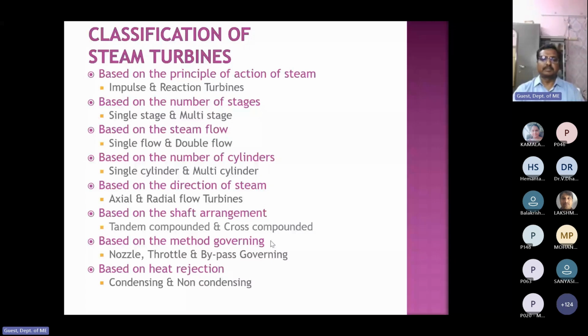So this governing system detects the speed of the turbine and opens the inlet valves of the turbine, so the turbine takes more steam and the load can increase. In a similar way, when you switch off the lights, the load on the grid decreases and turbine speed will increase. To normalize that speed, control valves close the steam input and bring it back to normalcy. In this power plant, the speed of the turbine is 3000 RPM, so we try to maintain 3000 RPM.